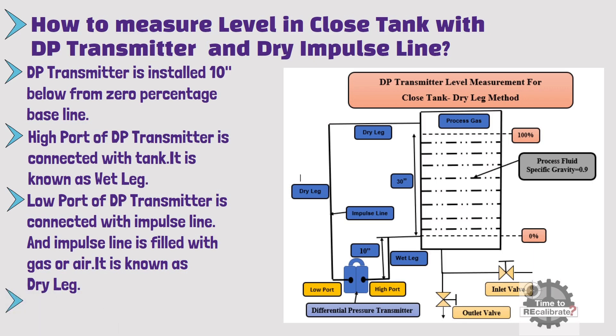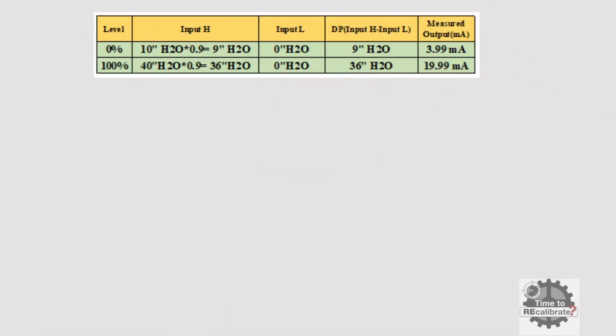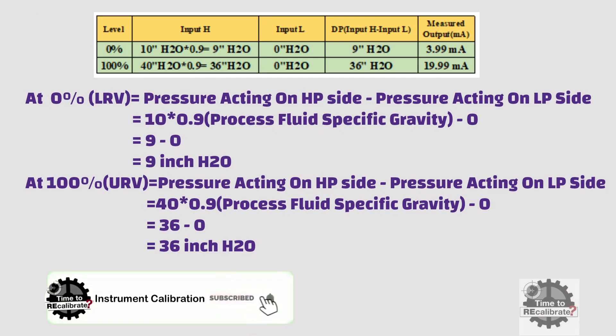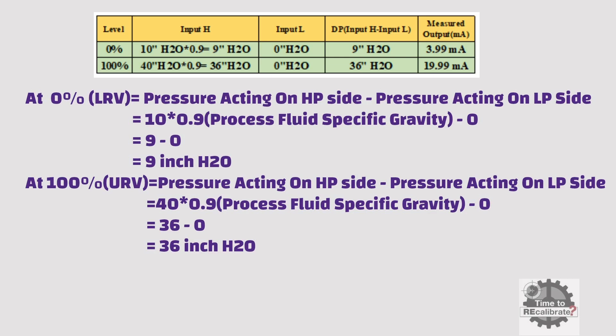Now let's assume that the process fluid's specific gravity is 0.9 in this example. Let's go to the calculation table. At 0% level, the DP transmitter high port side has 10 inch H2O pressure. This pressure is multiplied by the specific gravity of the fluid, which is 0.9 — so 10 multiplied by 0.9 gives 9. Therefore, at 0% level, the transmitter high port side has 9 inch H2O pressure. The DP transmitter low port side is connected with the dry impulse line, so it has 0 inch H2O pressure at both 0% and 100% level. Input high side minus input low side gives differential pressure, so differential pressure is 9 inch H2O at 0% level.